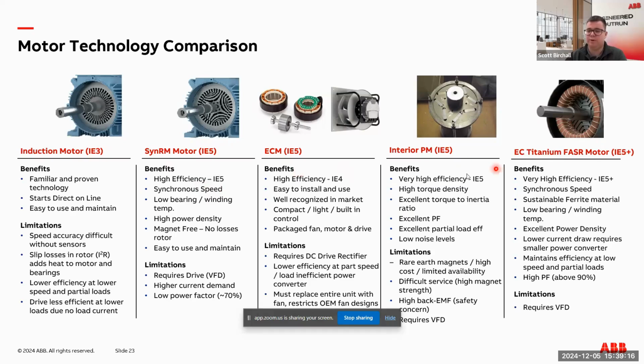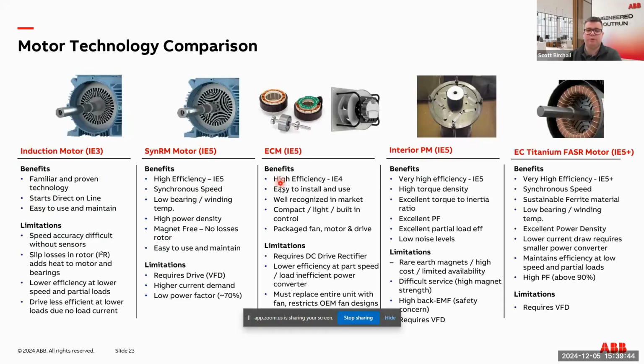As you can see, these bands - as Tim touched upon, the IE3, IE5 and so on - each band is, as Tim mentioned, 10% less losses than the last one. But I'd preface that and say don't just look at the band, because it is only a band. You could have two IE5 motors, for example, where one is at the top of the band and one is at the bottom. Also, these bands are based on full speed as well.